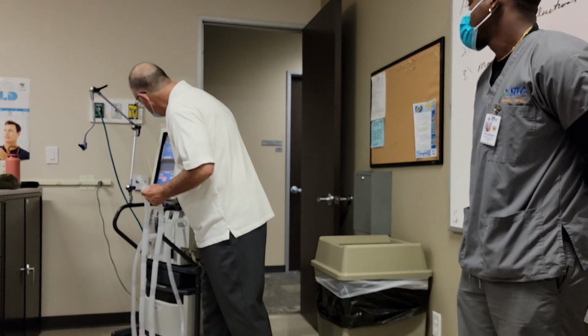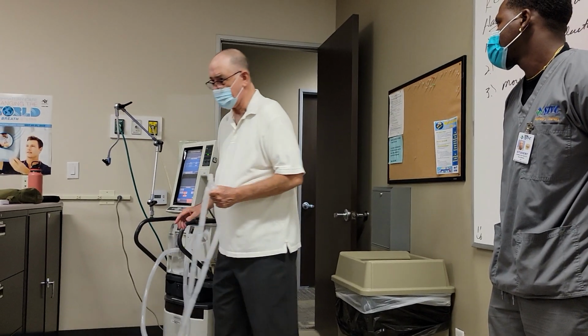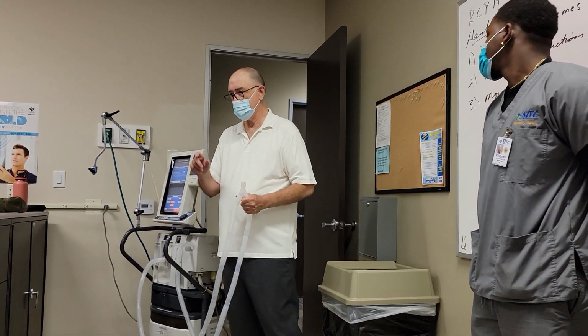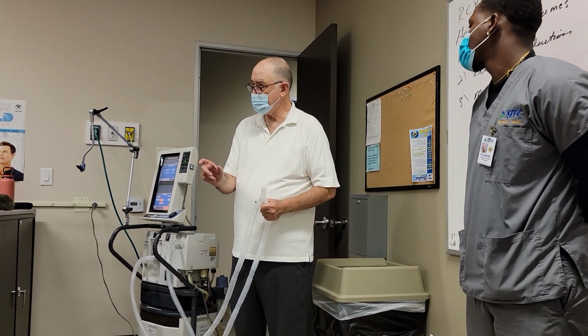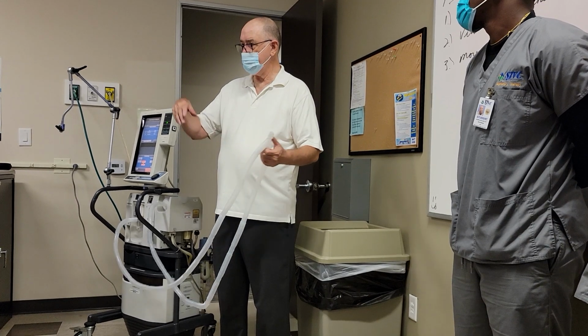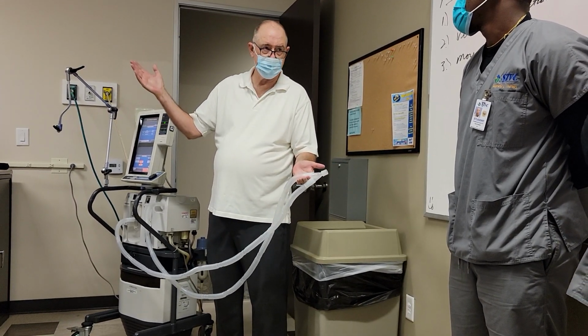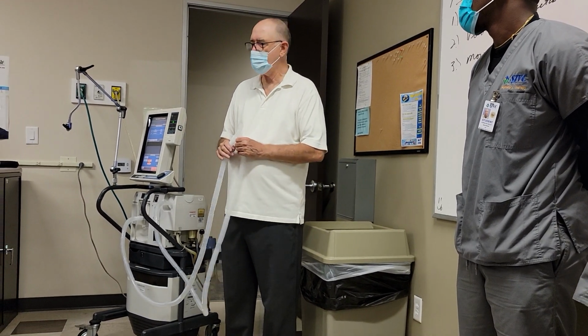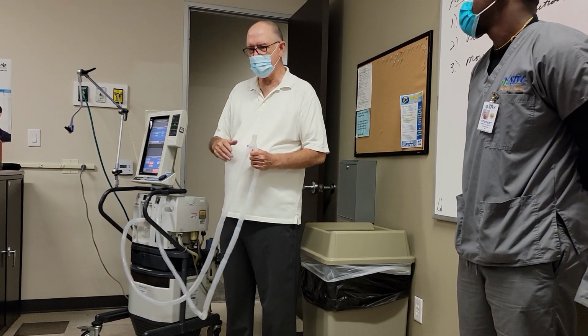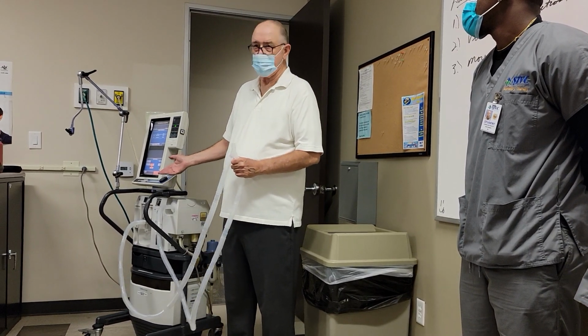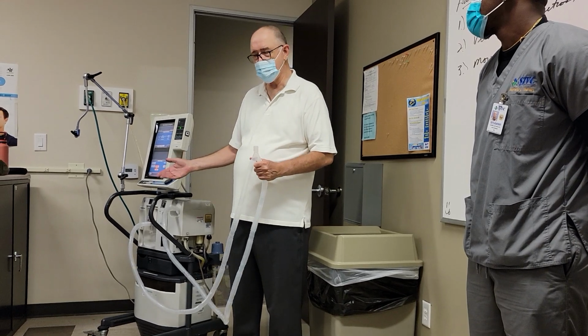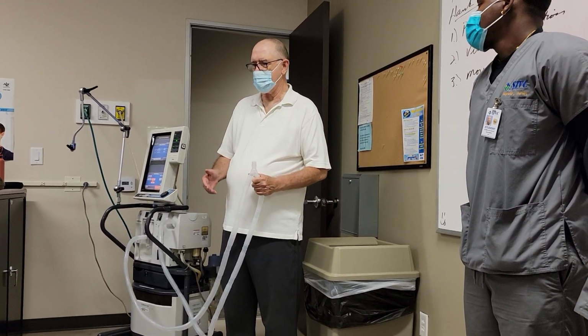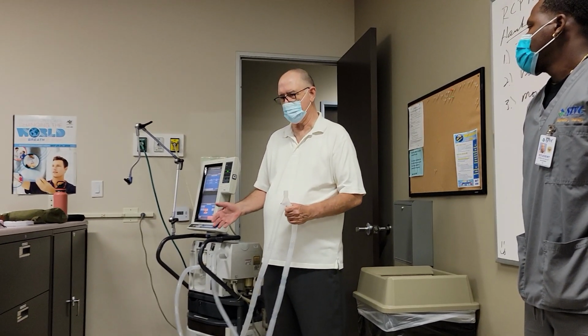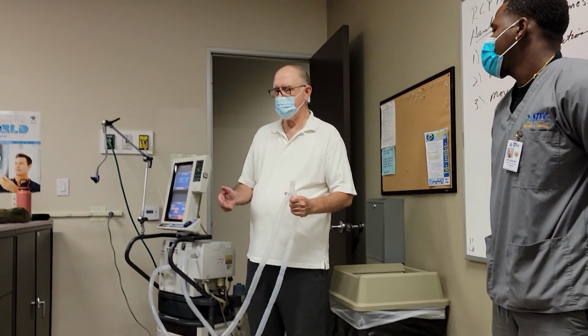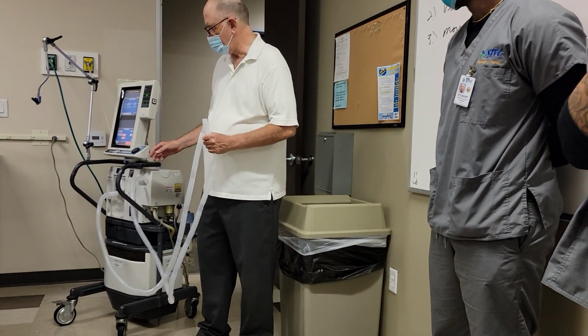Or I could do pressure control. There, I'm controlling the pressures. Volume, who knows? Okay? If the patient is spontaneously breathing, yeah, that's a good mode. Okay? It's got some limitations, got some issues, but you've got some degree of control. But not as much as with volume control.